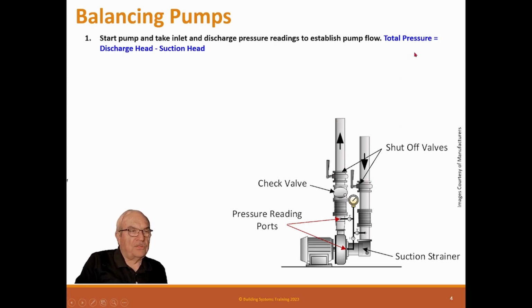So total pressure equals the discharge head minus the suction head. Now that may not seem too intuitive to you, but it's that way just in case you happen to have suction pressure below 0. If you do, then it becomes a plus and it adds to it. But otherwise, if you have 10 psi coming in here and you have 50 psi going out, the differential is 40 psi. So the equation is really simple.